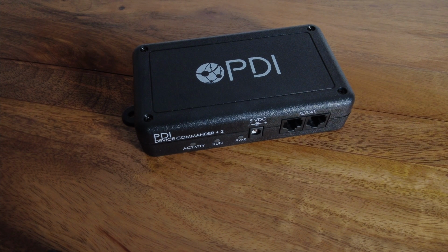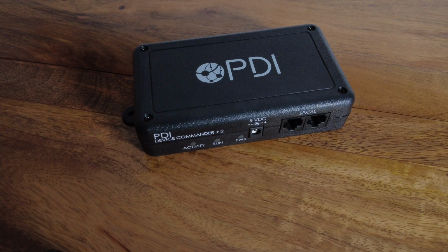Aside from the occasional long wait for a PDI help desk representative to call you back and do the actual setup, this is a very quick, very easy device to configure and to set up. I mean, there's zero configuration on the technician side other than whatever serial settings you choose to set up in the tank monitor. Now, if you're dealing with a Veeder-Root, you do need to have an RS-232 card.